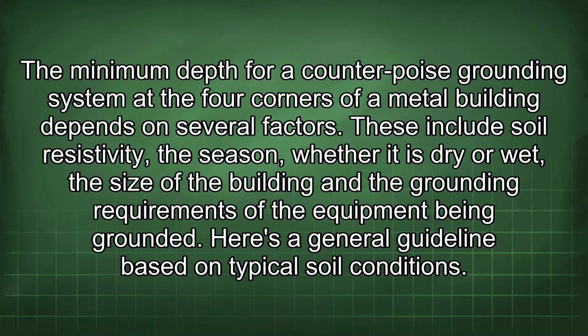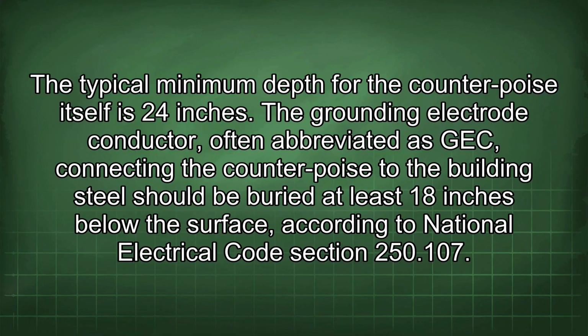The minimum depth for a counterpoise grounding system at the four corners of a metal building depends on several factors. These include soil resistivity, the season, whether it is dry or wet, the size of the building, and the grounding requirements of the equipment being grounded. Here's a general guideline based on typical soil conditions. The typical minimum depth for the counterpoise itself is 24 inches.